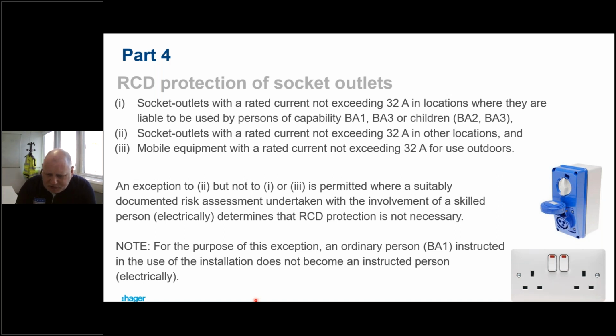There's a couple of examples I can think of where we might be able to use this. So if we've got a plant room in a high-rise block of flats or something like that, we may have a socket underneath maybe a TPN board that is for supplying equipment in that plant room. That plant room will have restricted access. It will be a locked door, and the only people going into that room, hopefully, will be electrically qualified people. So we've got to be very, very careful how we apply this risk assessment, but we can do it if we really need to.